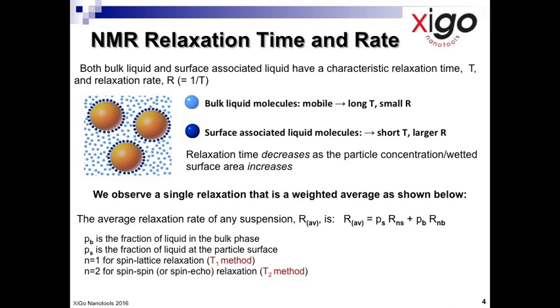The relaxation time decreases as the particle concentration and/or the wetted surface area increases. A suspension of particles in a liquid with a large wetted surface area — for example, a nanoparticulate pigment — will have a smaller relaxation time than a suspension with a small wetted surface area, because there will be more liquid molecules associated with the particle surface. In general, the higher the solids loading, the greater is the measurement precision. Since a vast number of industrially useful suspensions are manufactured or used as concentrates, XiGo measurements can prove very useful as they can be made using undiluted suspensions.